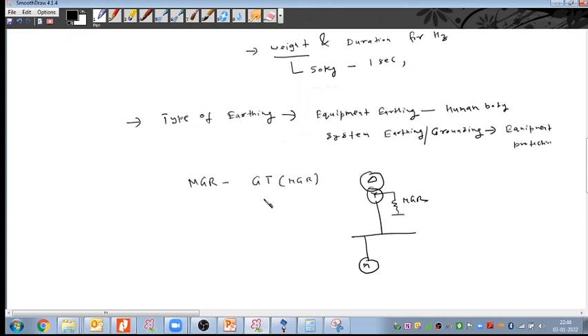In other ways, we can use NGR for a distribution transformer, or for that matter any sort of LV or medium voltage transformer which is feeding power to motors or pumps, inductive loads, rotating equipment. In that case, yes. Otherwise, other than this, NGR is not a mandatory requirement.